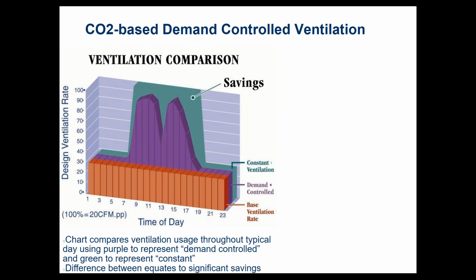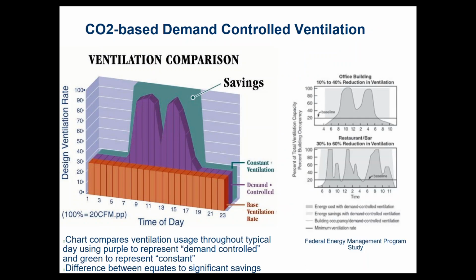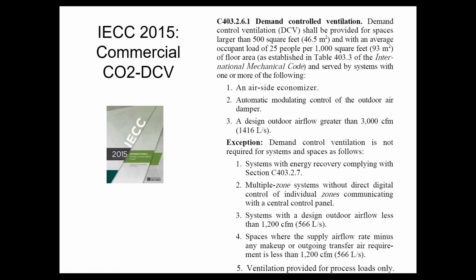Demand control ventilation is also a requirement per the code. We'll dive more into that in 2 weeks. But if you don't know what DCV is, demand control ventilation, it's a way to lower the ventilation amount below the mechanical code's required minimum ventilation on times when the building is less occupied. Typically use a CO2 sensor to measure how occupied the building is and then cut back that ventilation when less people are there. With the idea being hardly any building is 100% fully occupied at all times. That's required by code in lots of applications.